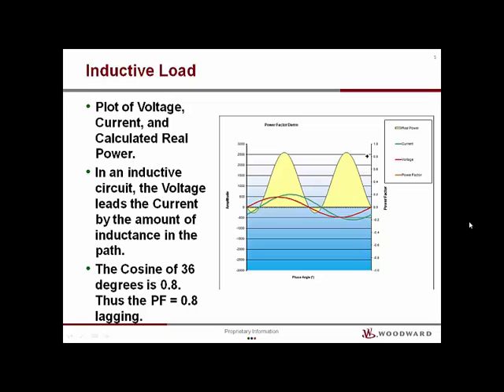This plot of voltage, current, and calculated real power is an AC generator with a purely inductive load. Due to the inductive reactance nature of a coil, the current is delayed behind the voltage. In this case, the shift is 36 electrical degrees. The cosine of 36 degrees equals a 0.8 lagging power factor.